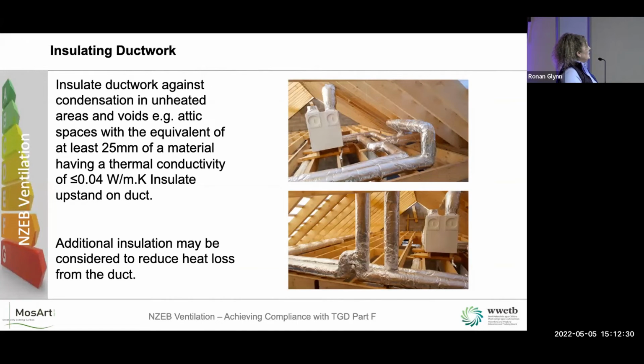So this duct here is running all around the house. This is the same attic and all the way, and then it ends up way down there. It would take an awful lot of pressure off the fan if it just went from A to B there without running all around the house. Now, I get that people want to floor out their attic and use it as storage, but to be honest with you, the ventilation system deserves to be looked after as well.